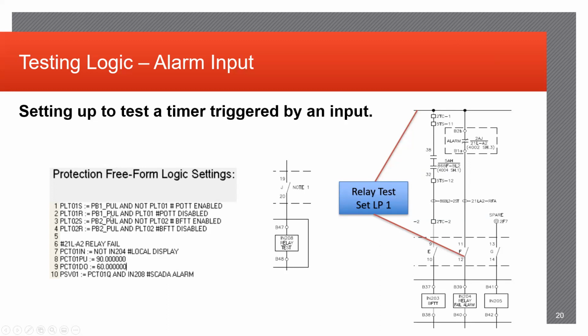You can also see that if there's other logic that may be going into that input, such as a push button, a switch that may be associated with it, any other contacts from other relays or a piece of equipment, that you utilize those as well and indicate that the input from the relay picks up when necessary.